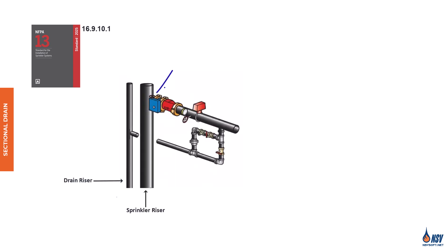Imagine a multi-story building where maintenance is needed on the sprinkler system of just one floor. Naturally, you want to avoid shutting down the entire system, so what should you do? According to Section 16.9.10.1 of NFPA 13, 2025, buildings exceeding two stories must be equipped with a floor control valve, check valve, pressure gauge, drain valve, and flow switch. These components provide isolation, control, and annunciation of water flow for each individual floor. This means you can safely shut down and service one level of the system without affecting the rest of the building. However, this requirement may not apply if the total area of all floors combined does not exceed the system protection area limitations specified in Section 4.4.1. We'll explore this topic in more detail in upcoming videos. Now, let's explore how sectional drains support this kind of localized maintenance and drainage.